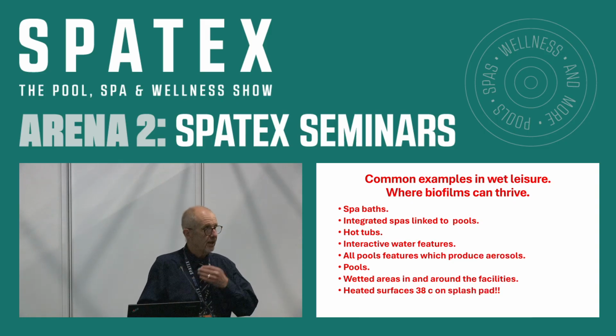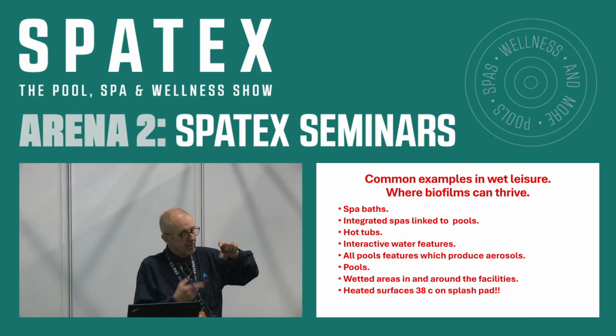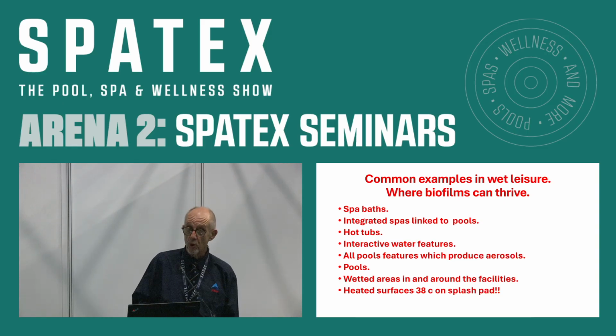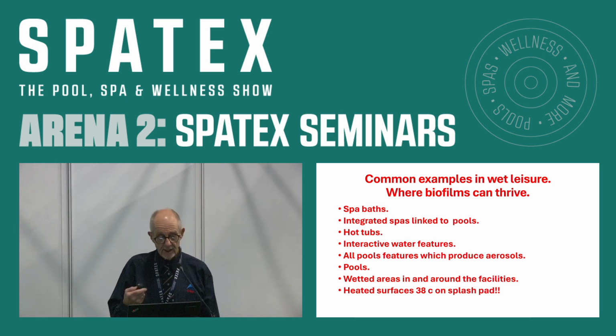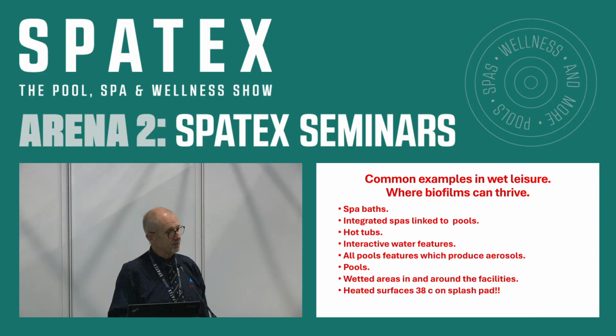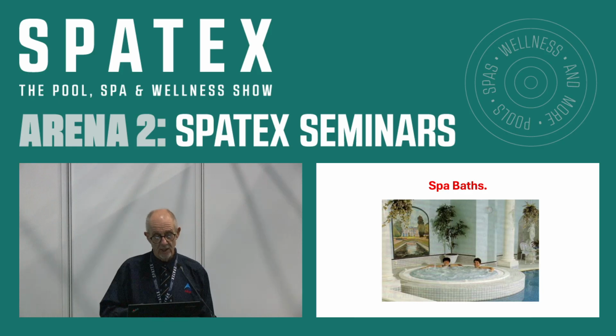I was talking the other day, and somebody was saying about these letterbox overflow channels, about that wide, and they constantly get wetted on the top side, and they were getting poor bacteriological results. So I said, well, you need a method of cleaning that effectively. Wetted areas, heated surfaces. I've seen on splash pads with foam floors, cuts in the floors at 38 degrees. And you guessed it, I did a sample test on them, and they were absolutely infested with biofilms. So we need to be aware of what we're dealing with and where it can be.